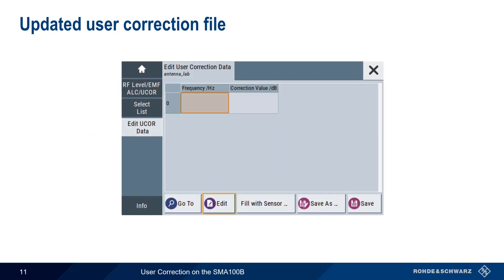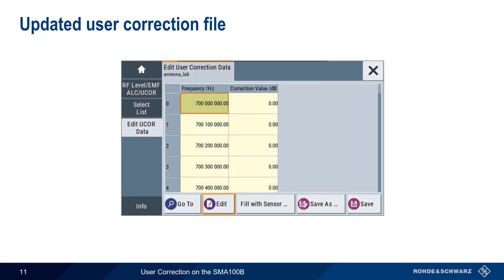Our previously empty user correction file should now be filled with data points in the Frequency Per Hertz column. We see steps every 100 kHz as we configured in the previous step. The correction value per dB column, however, is still filled with all zero values. The next step, therefore, is to fill these values with data from the sensor, so we choose Fill with Sensor.